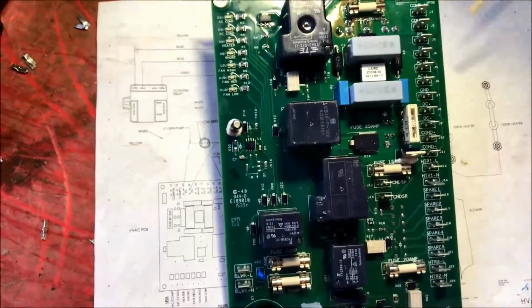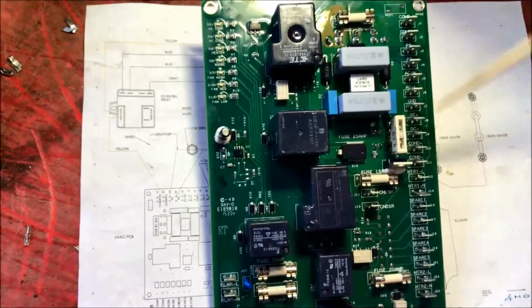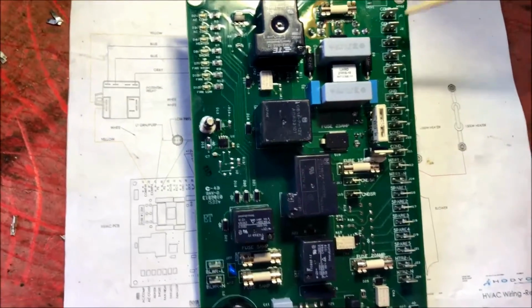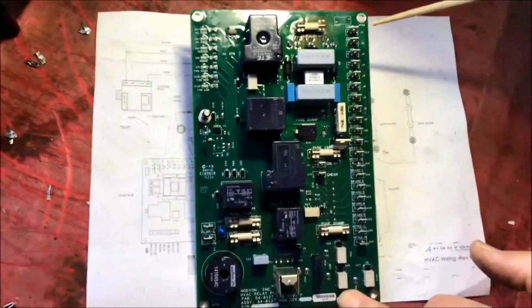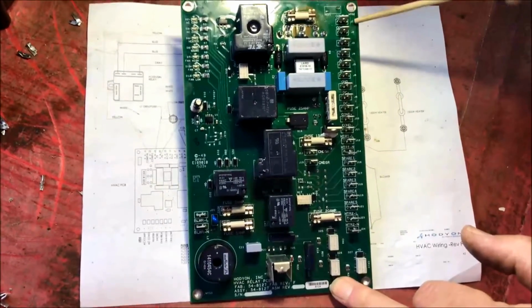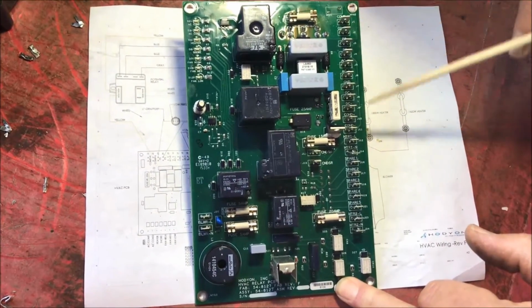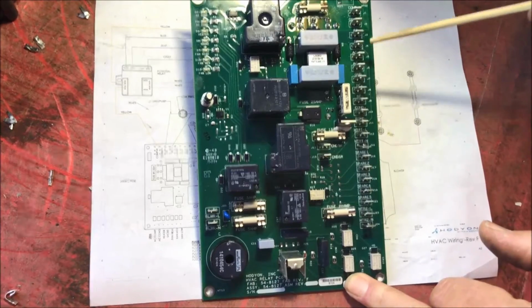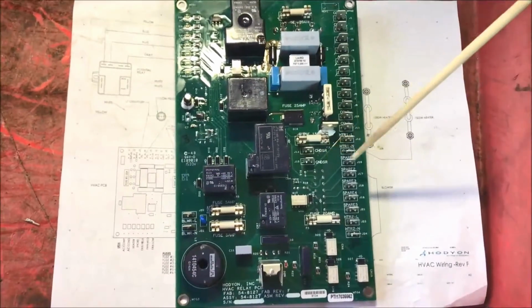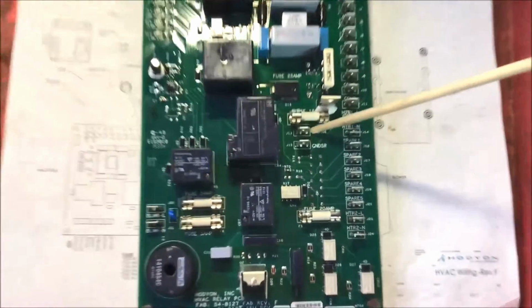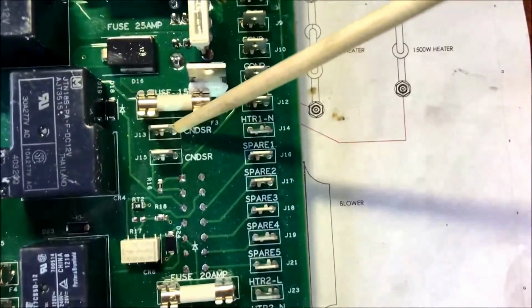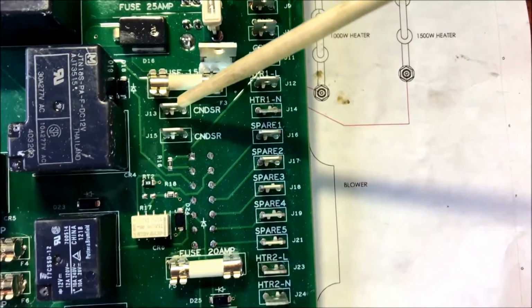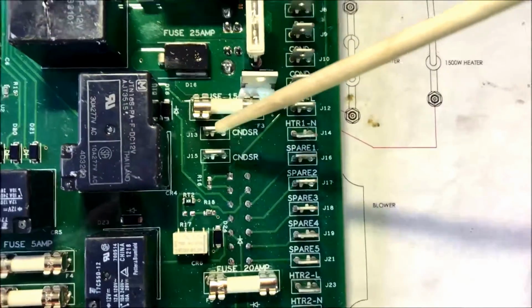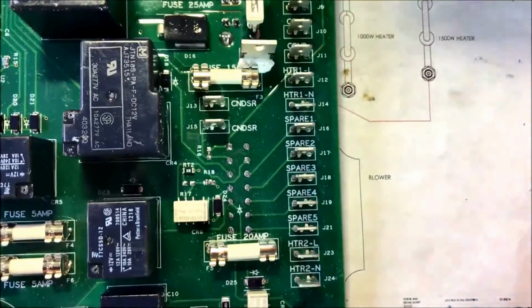I call this the rows of spades. These terminals are for the different components in the HVAC. It has both AC voltage and DC, so be very careful in this area. On the circuit board also are the terminals for the condenser fan activation. If you jump these two together, the condenser fan will stay on anytime the compressor is on.